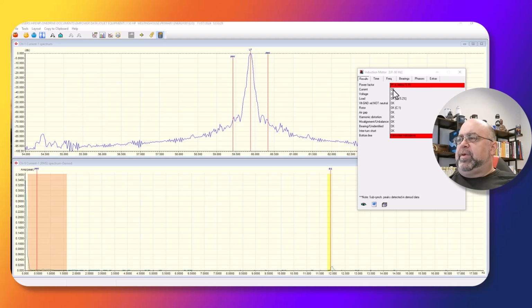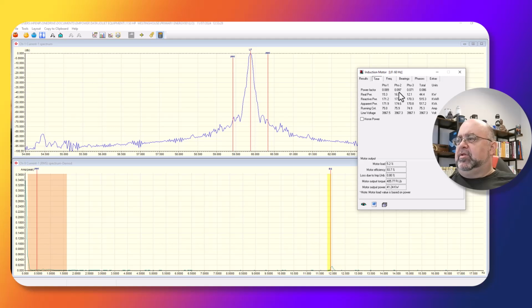It identified a low power factor. Says there's a light load on it, which is possible. We'll see that in a second. Could be the CTs were set up wrong. So when they took the data, they didn't rotate it, so it looks like the phases are rotated a little bit. Real power is very low, partially because of a very low power factor there. Current should have been showing a much higher percentage, but we're alright. Not much of an impedance unbalance, things like that.